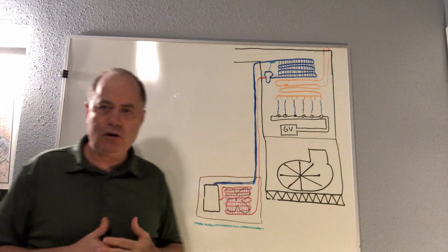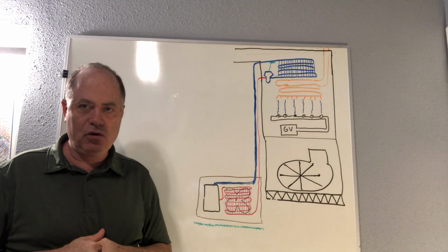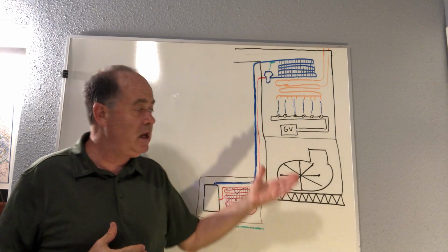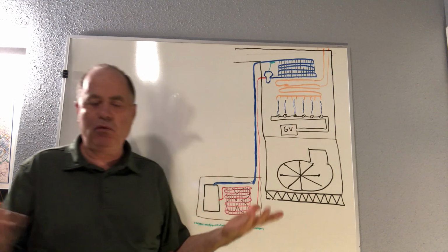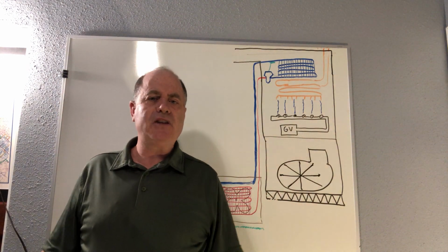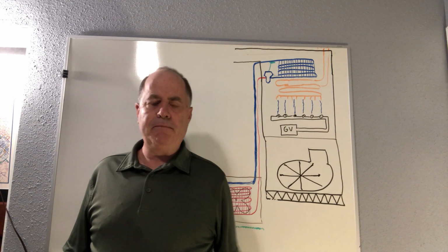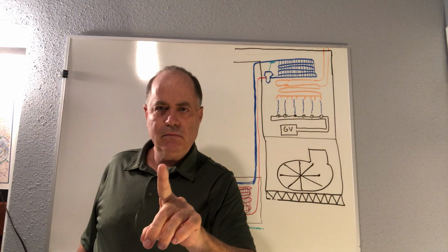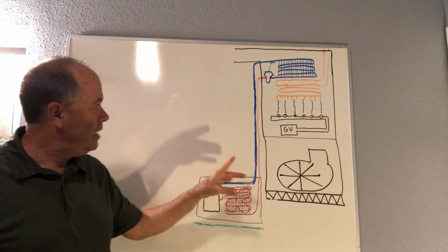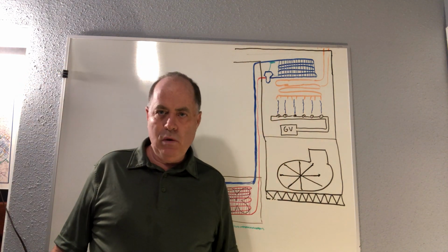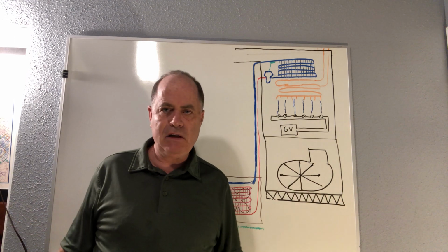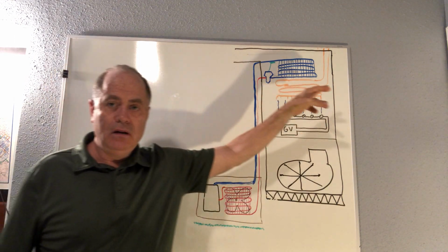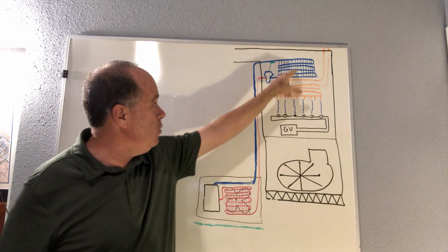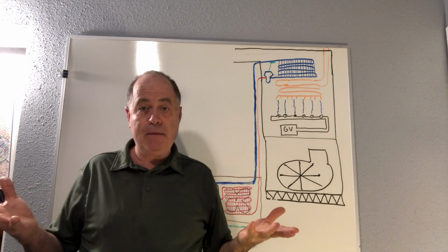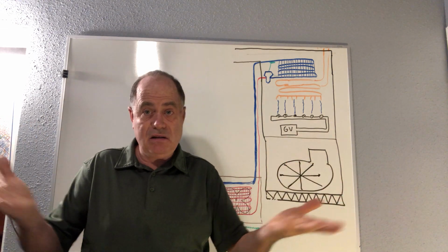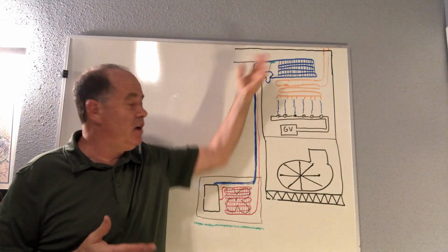Is it when we're running the cooling? No, it's not when we're running the cooling, because when we run the cooling, the pressure on the low side drops down. You'll say, well, I know the answer, Mr. Needham. Of course, it's during the off cycle. It's when the unit's not running, then the low side pressure is higher. That's the right answer. No, it's not. It's actually when we're running in heating mode. When we're running in heating mode in the winter and you're not thinking about it, that's when you have 120, 130 degree air blowing right onto your evaporator, and the pressure temperature relationship stays, it's still valid, and that's when you have the highest pressure.